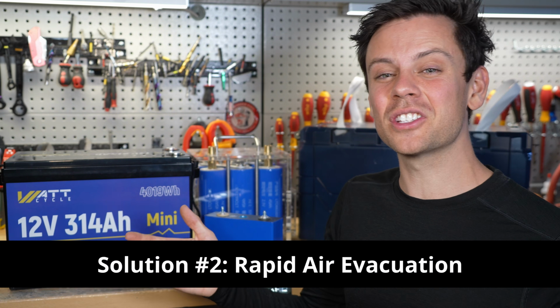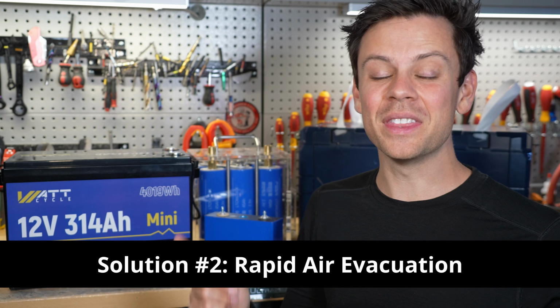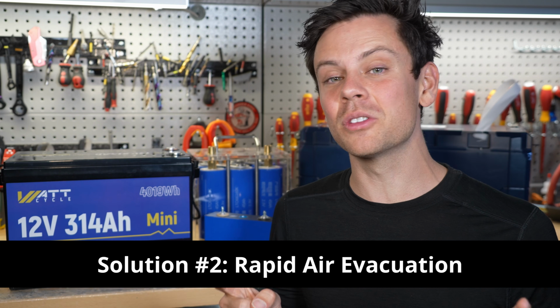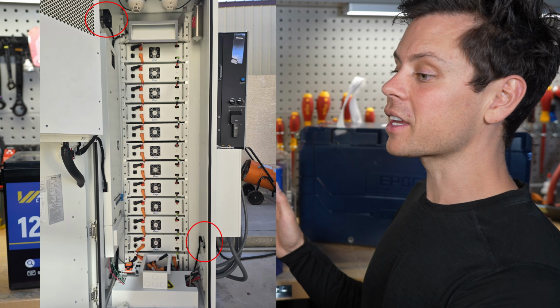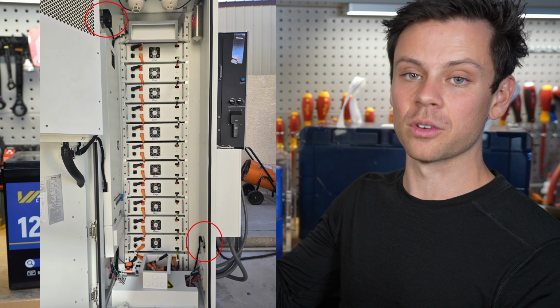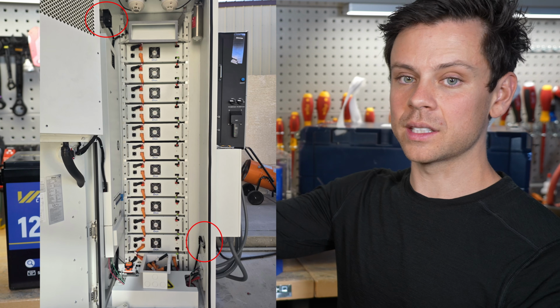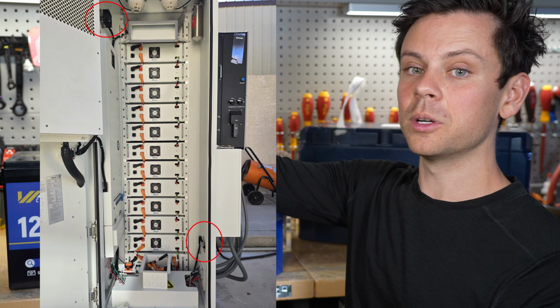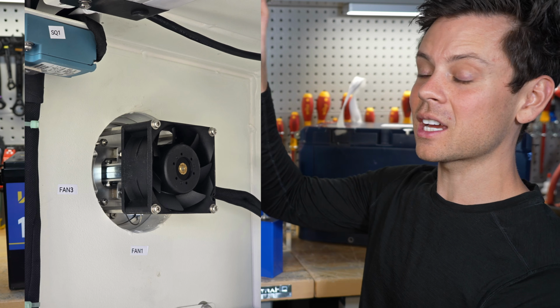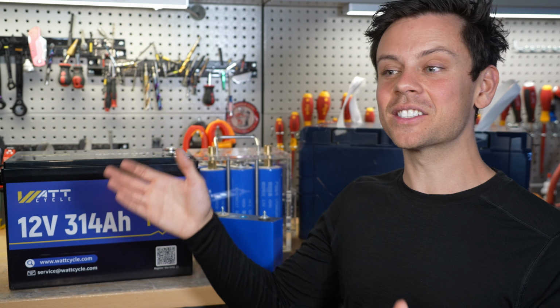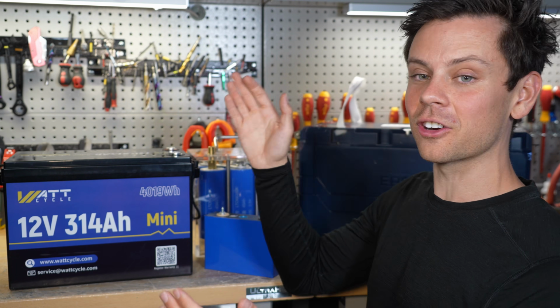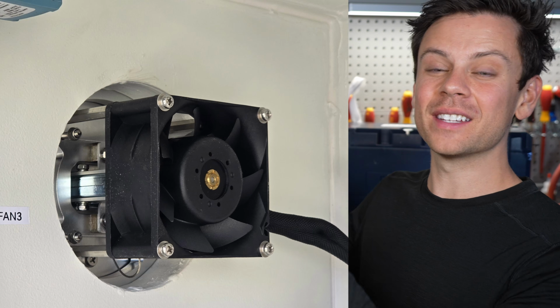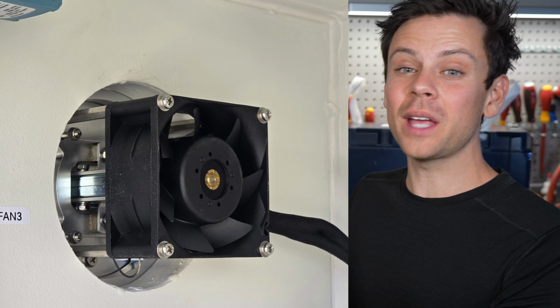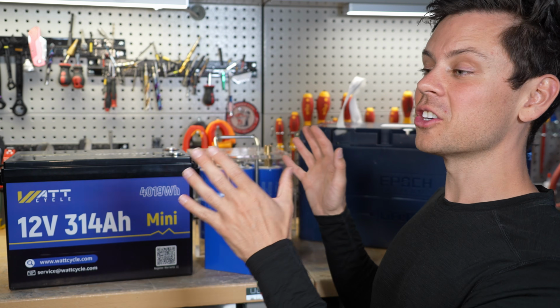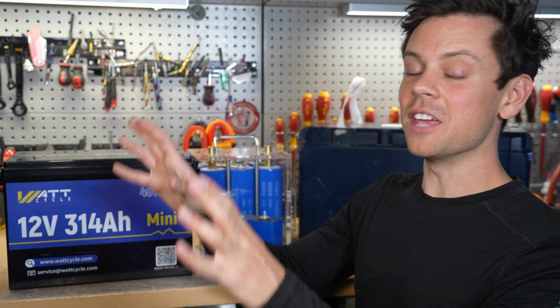The next solution is ventilation systems like evacuation fans, but this needs to be done by a professional or you need to do the math properly. My high voltage battery cabinet has evacuation fans for this reason. One's on the bottom, one's on the top. The bottom one sucks air in and the top one pushes air out, and they're designed for that capacity of battery. They have a heat sensor and a gas sensor, and they only open and turn on when there's a problem. The fans need to be designed for that purpose, and you should probably have redundancy built into the system, meaning its own power supply or battery backup if the main battery were to fail, because you have to power it off of something, right?